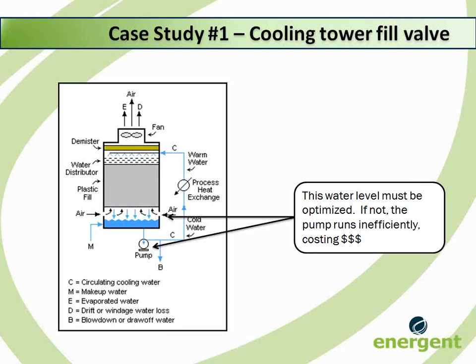If the water is too low, the pump has to work much harder to maintain that constant level of water throughout the system. When an electric pump has to work harder, it takes more electricity to run that pump, therefore more money. In this situation, the fill valve at the client site was broken. Monday to Friday, a facility operator manually filled the cooling tower to ensure levels stayed at the optimum size. Well, what happened on weekends and during holidays when the operator isn't on site? Well, let's see if we can find out.